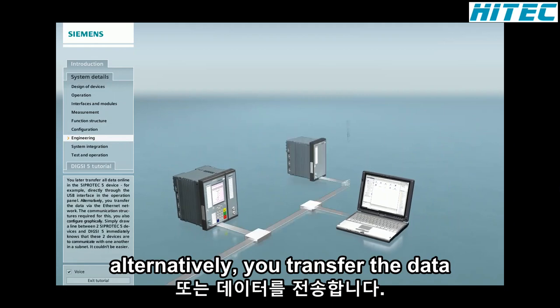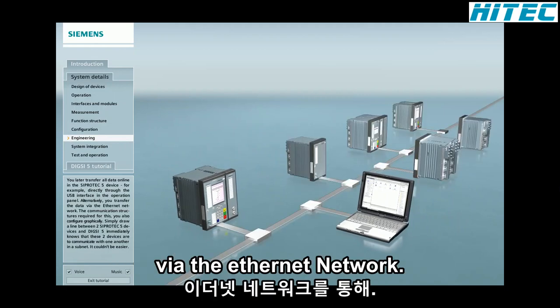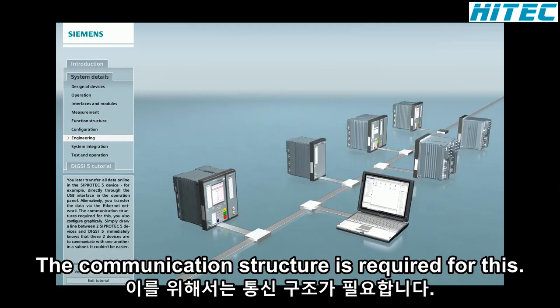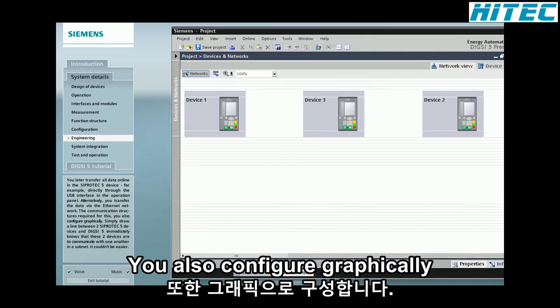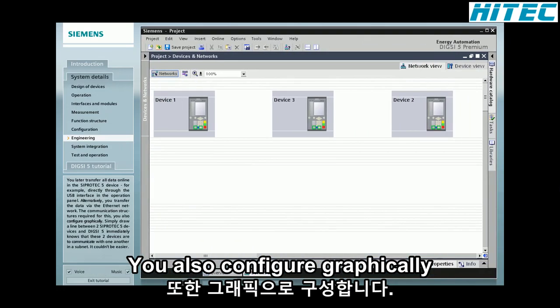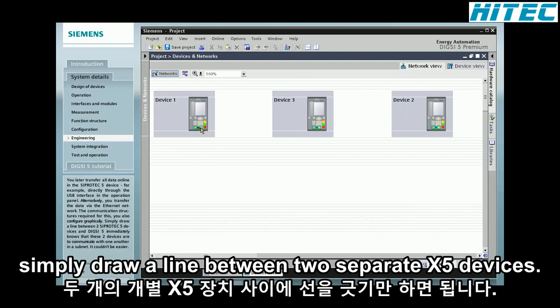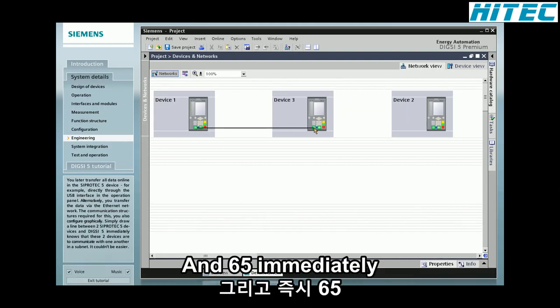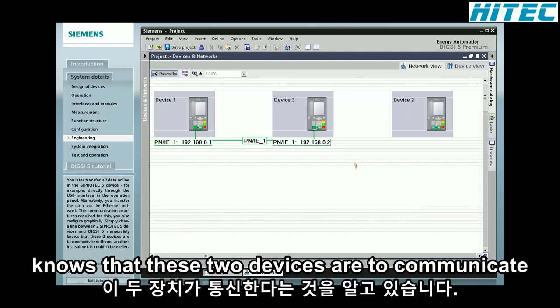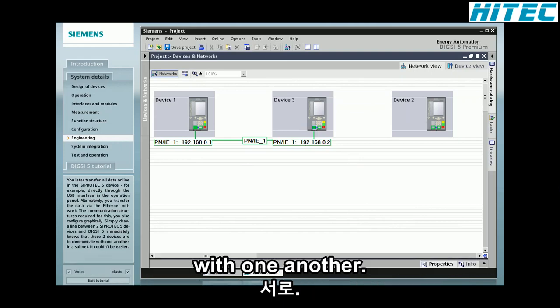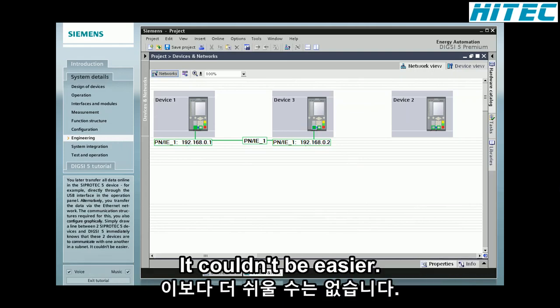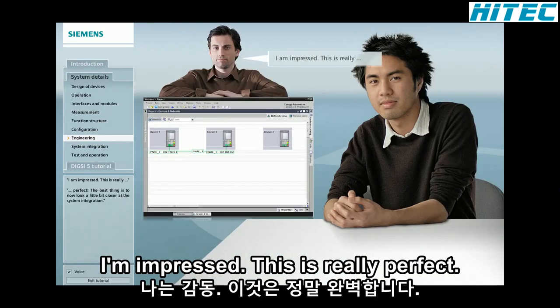Alternatively, you transfer the data via the Ethernet network. The communication structures required for this you also configure graphically. Simply draw a line between two SIPROTEC 5 devices and DIGSI 5 immediately knows that these two devices are to communicate with one another in a subnet. It couldn't be easier. I'm impressed.